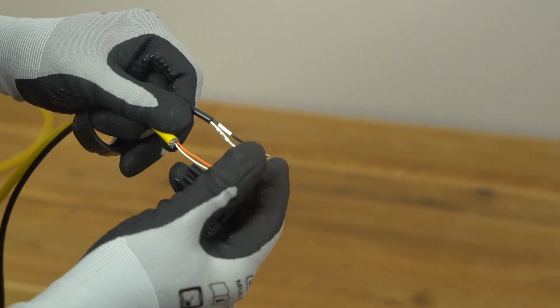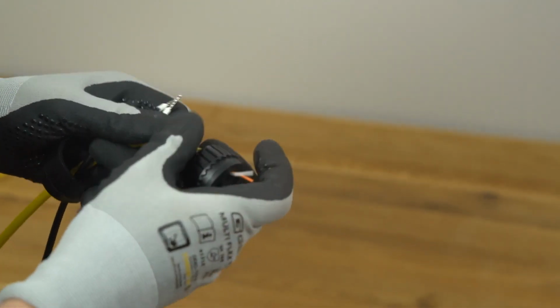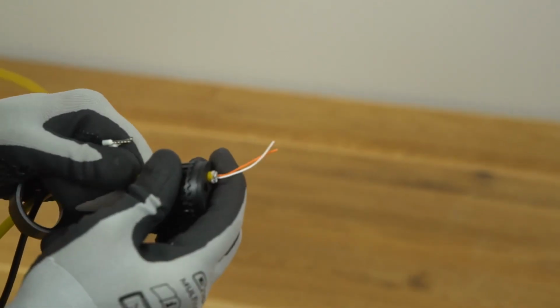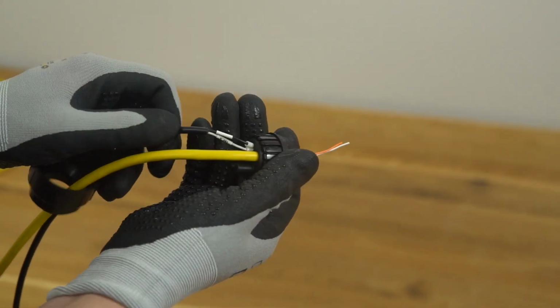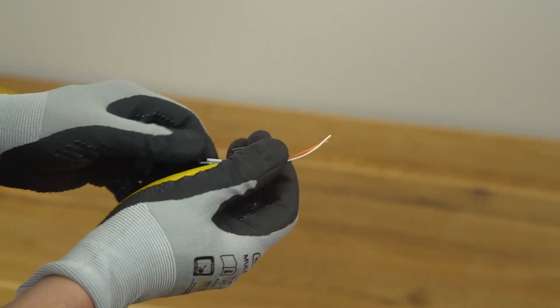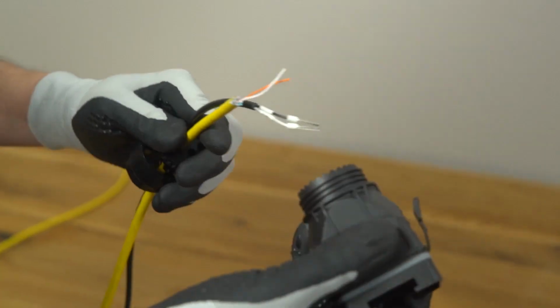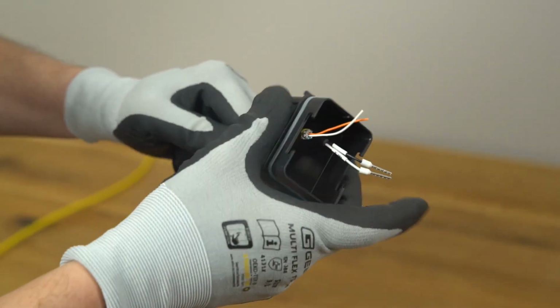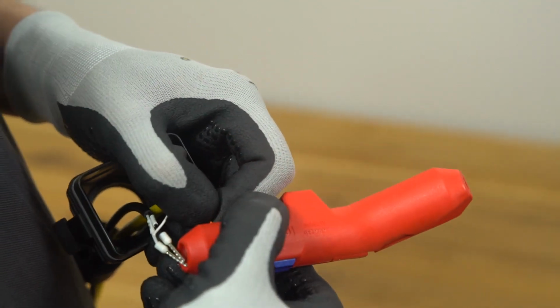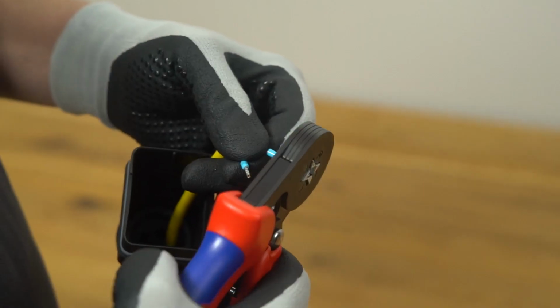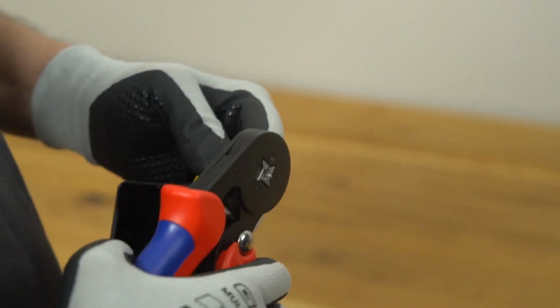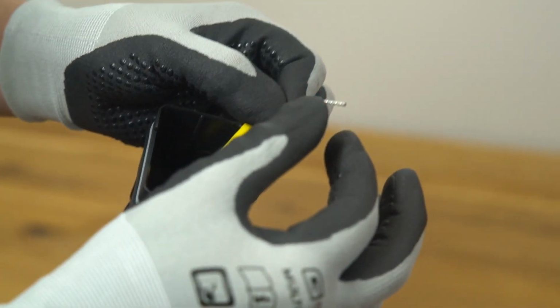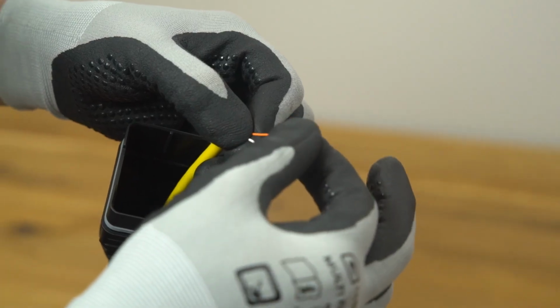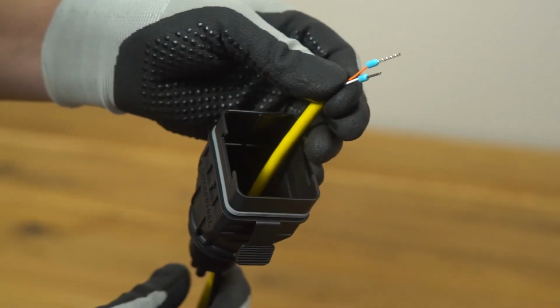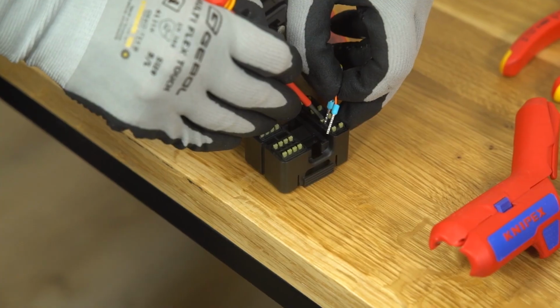For single-strand wire, remove approximately 4 to 5 centimeters of the cable sheath of the communication cables. Then strip approximately 7 to 10 mm of the inner cables. If necessary, you may have to fit the cables with end sleeves before you push them into the plug. For multi-core, multi-strand wires, remove approximately 4 to 5 cm of the cable sheath of the communication cables. Then strip approximately 12 to 14 mm of the inner cables.